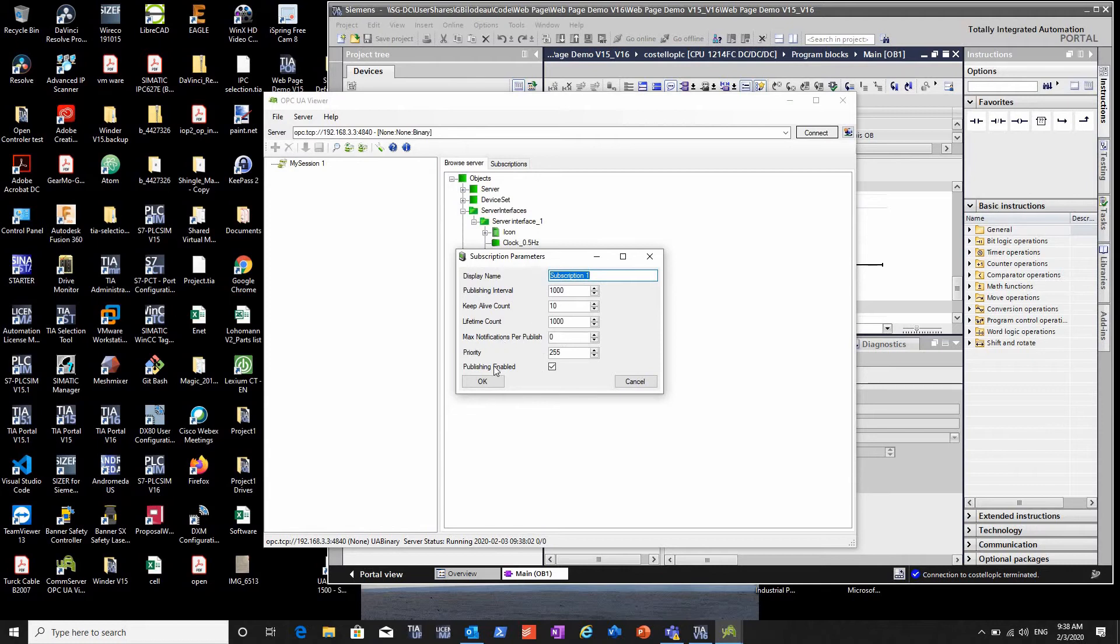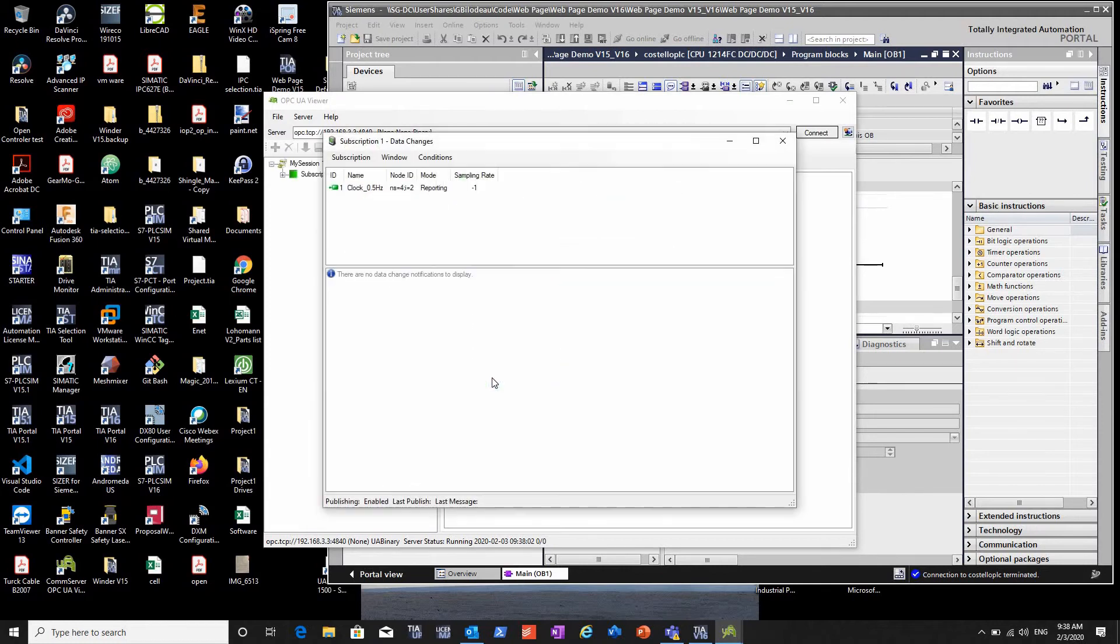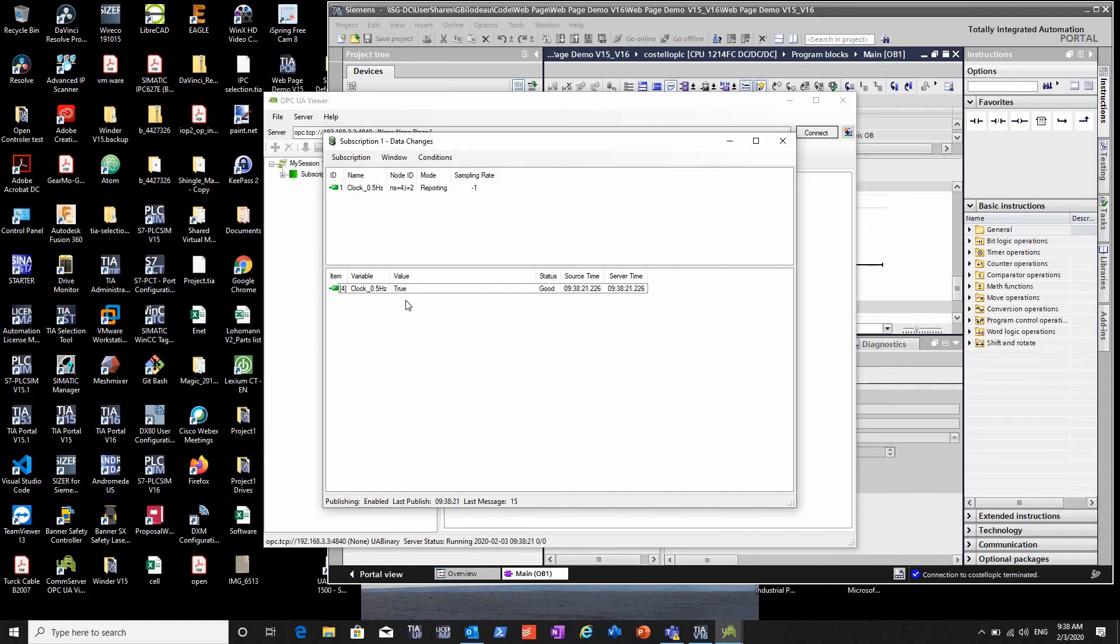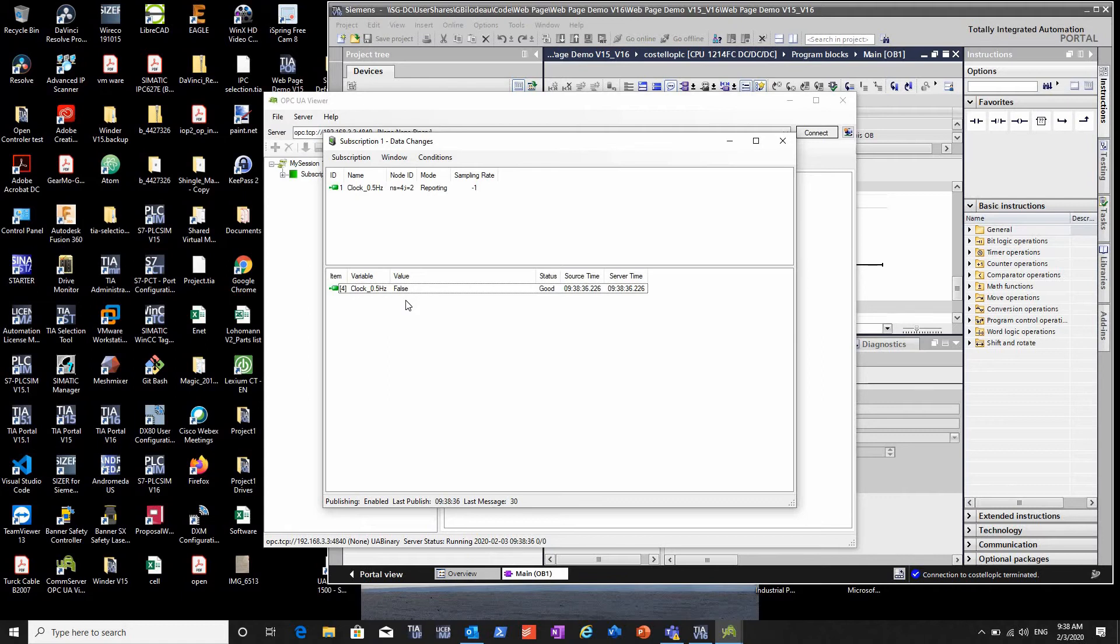Now I'm telling it to subscribe. You can see the value will be changing because it's reading it, and I told it to read once a second. The faster you read it, the more communication load you put on, so pick your update times according to what you really need for historians or control. It does put more comm load and processor load.